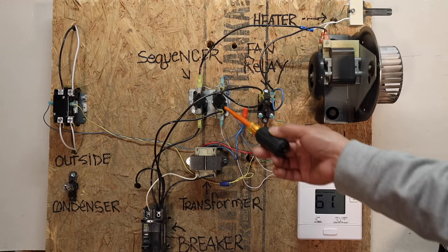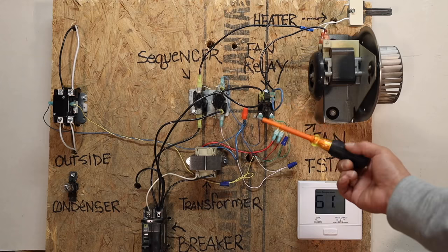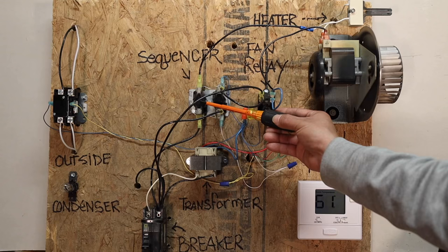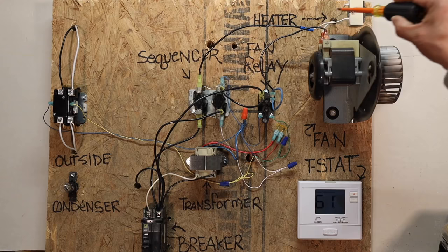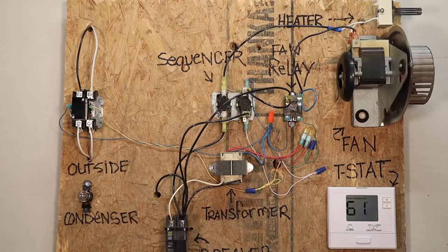At the same time that that's happening, these here are on a time delay, or on what they call a time sequence. So this one will energize first. Meanwhile, a minute to two minutes later, this one will energize, which is hooked up to the heater side of the system, and there's a specific reason for that.